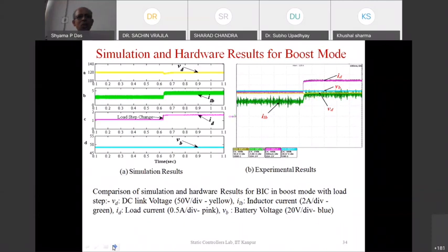Now, what we do here is that whenever there is a change in the discharging mode, it is basically a voltage control mode. Whenever there is a load change, the grid voltage changes. That basically generates the reference ILB. The reference ILB is generated by the change in the DC grid voltage. We have already seen that we have two loops, one is the voltage loop, another is the current loop. The voltage loop generates the reference current, that is ILB, and the actual current follows the reference current. So the DC microgrid is again brought back to the stable situation, close to 120.